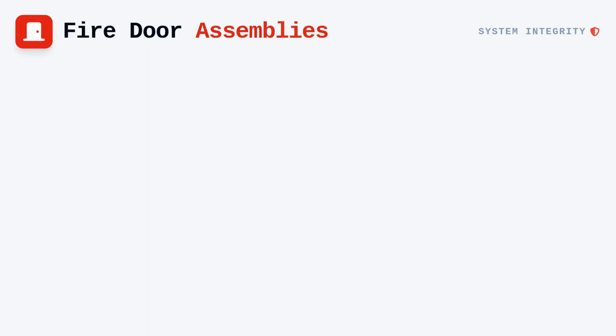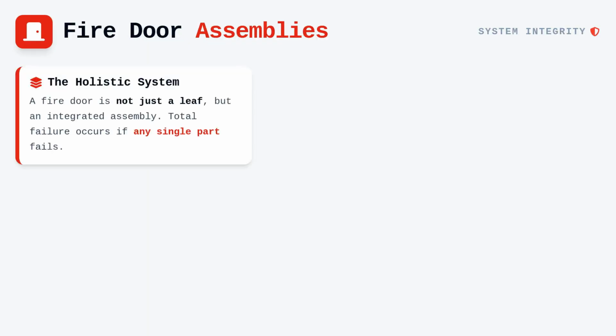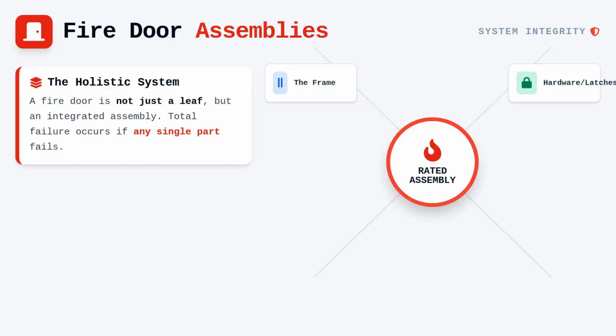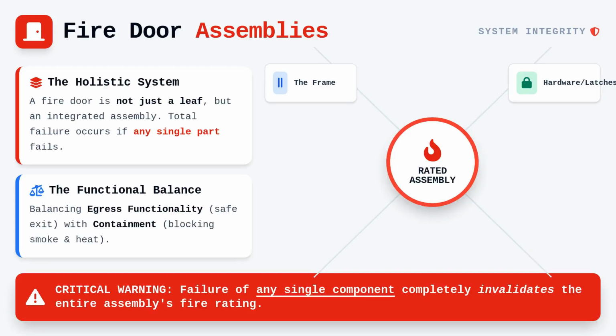The fundamental design philosophy relies on the assembly remaining closed and latched during the incident. We must understand that a fire door is not merely a door leaf, but a complete system consisting of the door, frame, hardware, and sealing elements. If any single component fails, such as a latch or an intumescent seal, the entire assembly may lose its fire rating. Maintaining this system requires precise adherence to listing and labeling protocols established by testing laboratories.